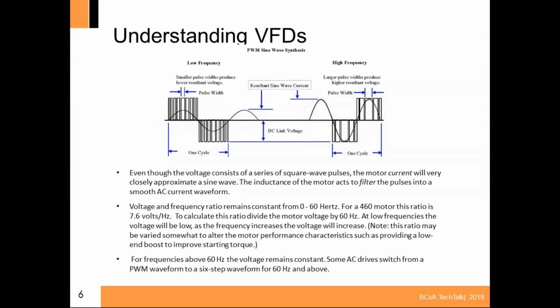Now, when the motor starts operating at 30 hertz, the wave is actually turned on and off. That pulse width really tricks the drive on the load side into looking at 230 volts at half speed. I say that, but in reality it's different just because they're non-linear. Just for understanding's sake, remember that when this motor is running at half speed, it's running at a much lower amount of voltage. And that is sometimes what bites you on these systems: the vendors will come out and want to minimize the cost of the thing, but it can be a detriment to what your owner wants done with the system.